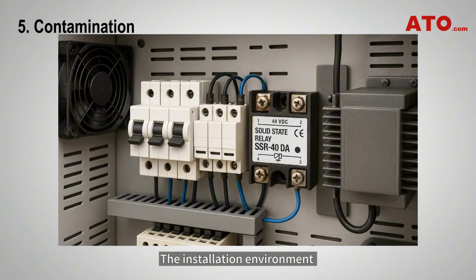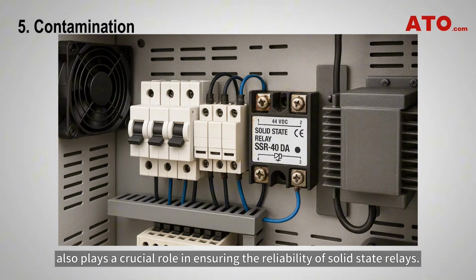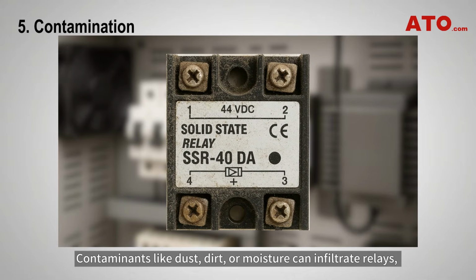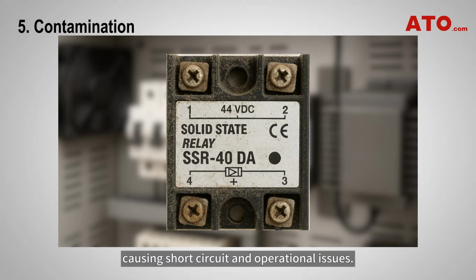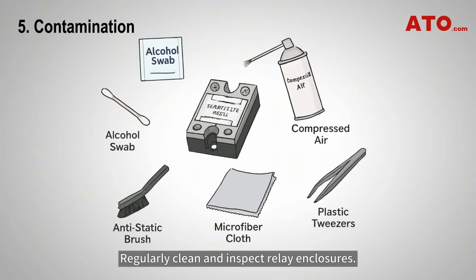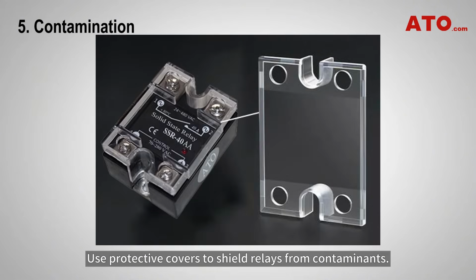Number 5. Contamination. The installation environment also plays a crucial role in ensuring the reliability of solid-state relays. Contaminants like dust, dirt, or moisture can infiltrate relays, causing short circuit and operational issues. Regularly clean and inspect relay enclosures. Use protective covers to shield relays from contaminants.